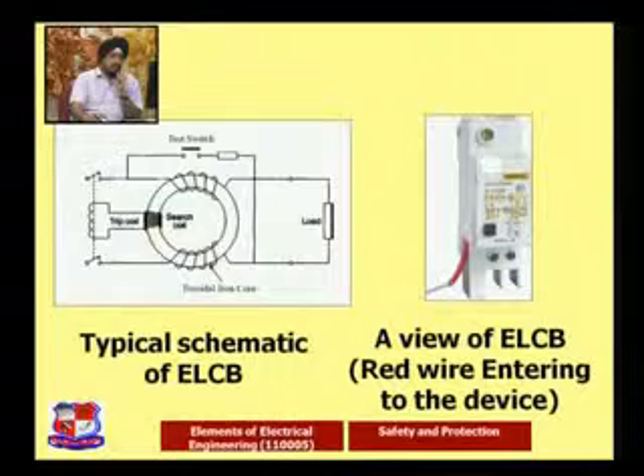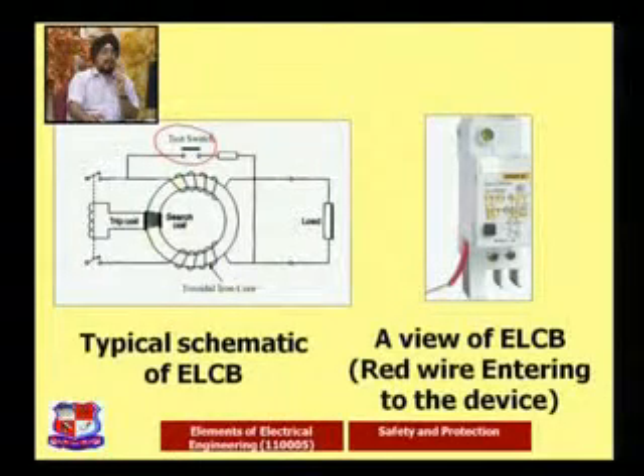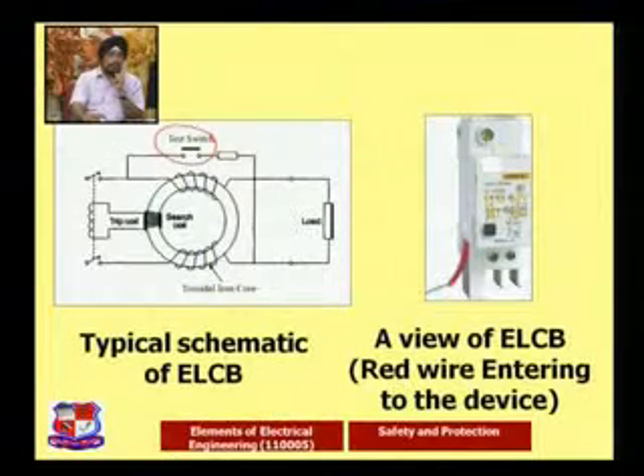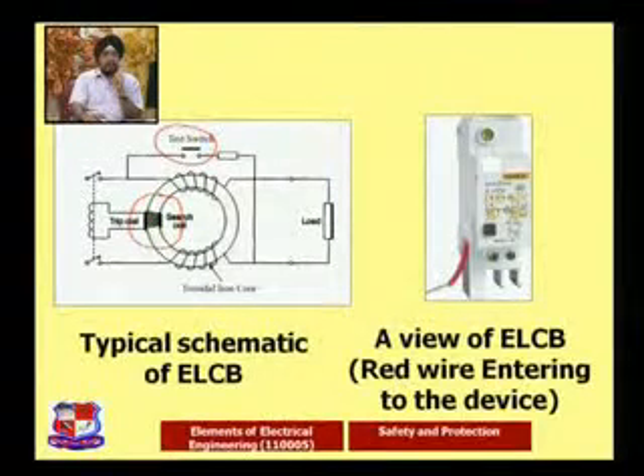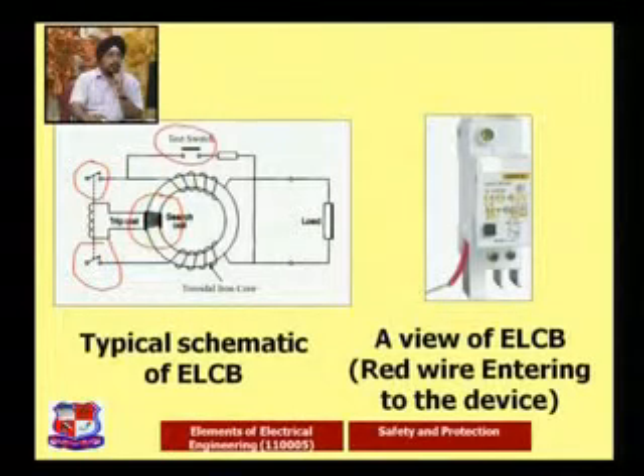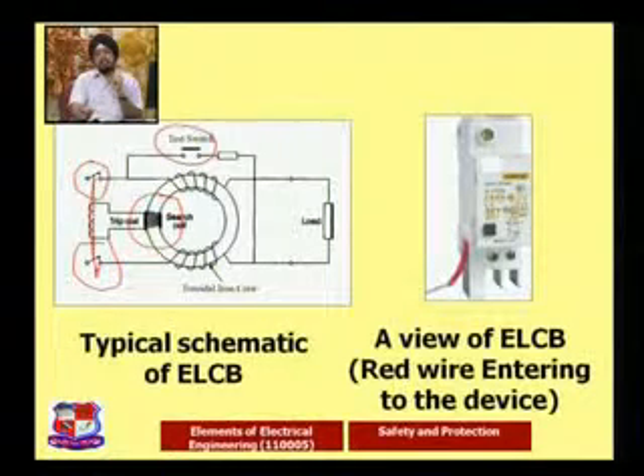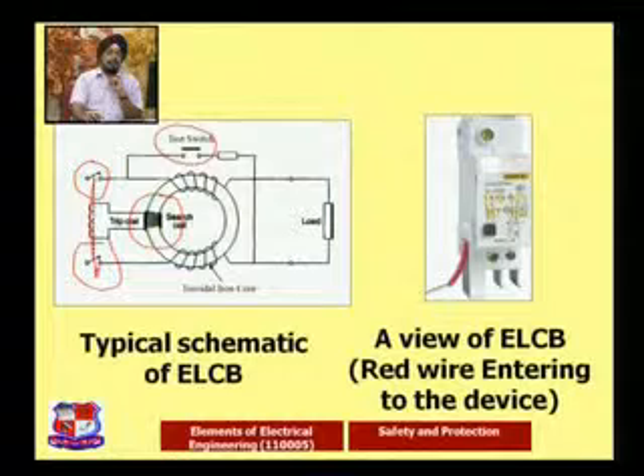We can see that a test switch or test circuitry is there. When we push that test switch, an abnormal condition is created in the circuitry, and this abnormal condition leads to the sense coil, which is connected with the trip coil. It senses that there is overcurrent and the condition is not proper. The contacts, the plungers, come downward into the closed condition, the trip signal is given to the ELCB, tripping is done, and the circuit goes to the open condition.